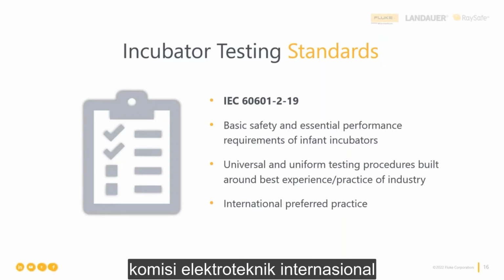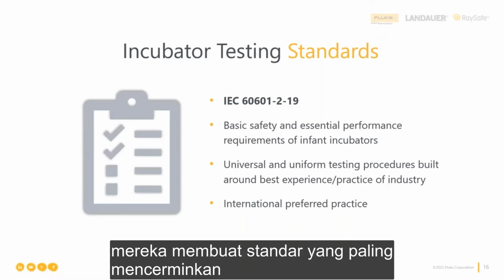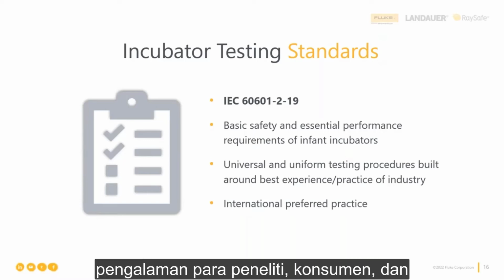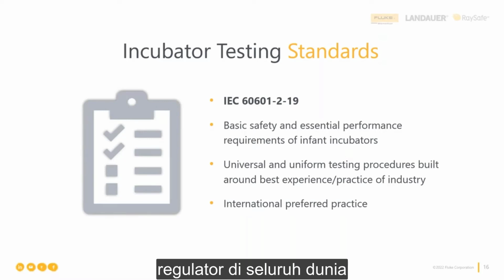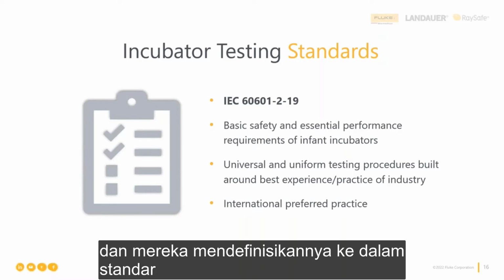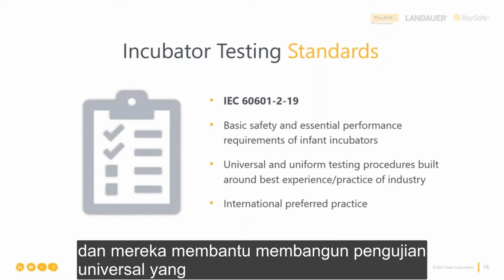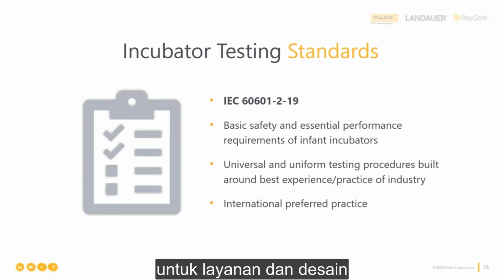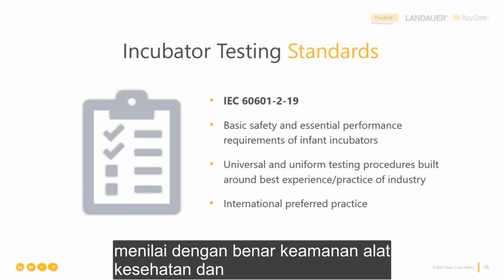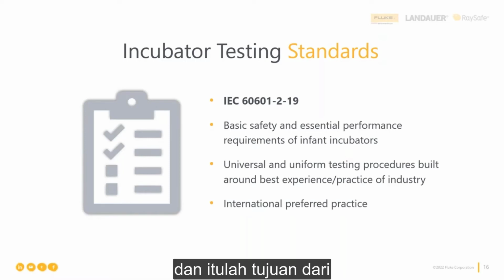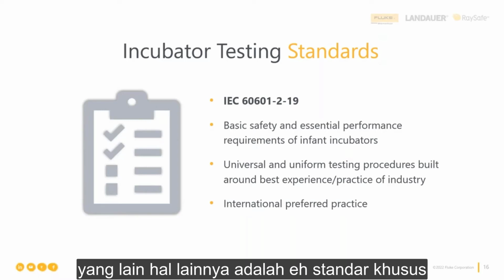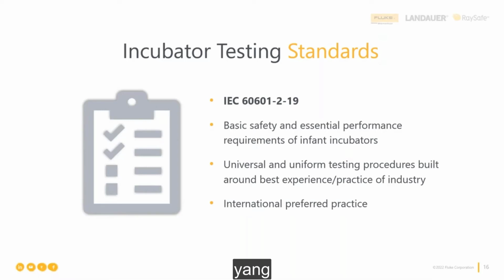The International Electrotechnical Commission, or the IEC, makes standards that best reflect the experience of the industry, the experience of researchers, consumers, and regulators worldwide. And they define those into standards, and they help establish uniform and universal testing procedures for biomedical service and design engineers to use. They're critical in helping properly assess the safety of medical devices and ensuring patient safety. And that's really the purpose of the IEC. The other thing is most local, national, or even country-specific standards have been harmonized to those IEC standards, which are recognized as the international preferred practice.